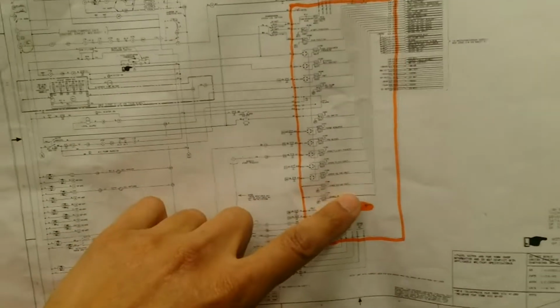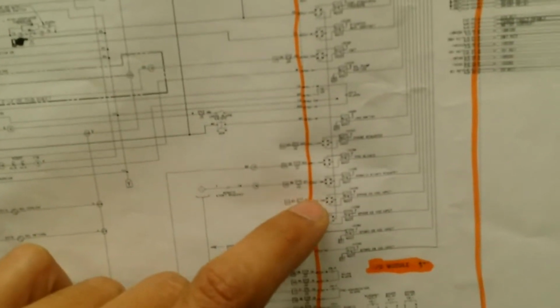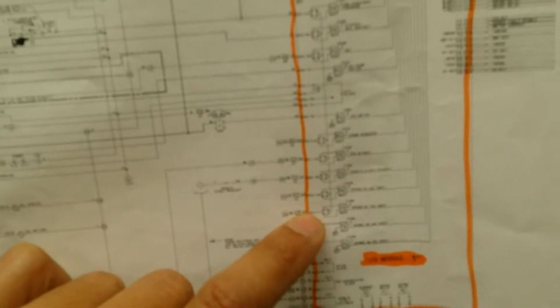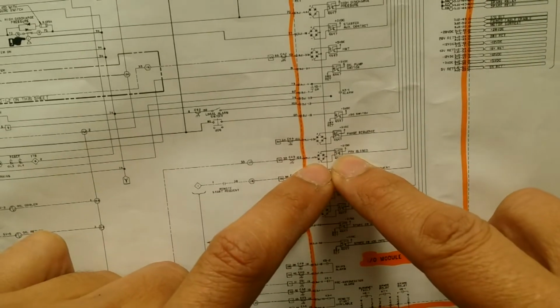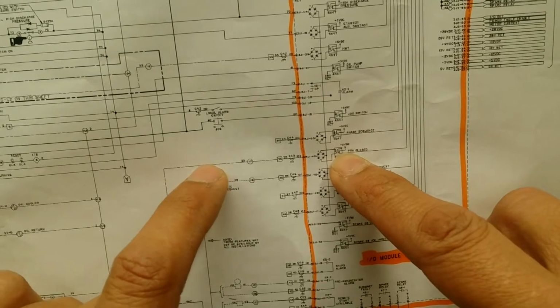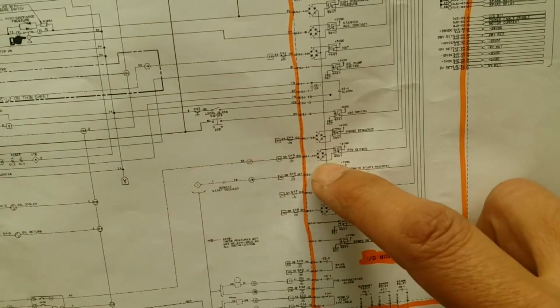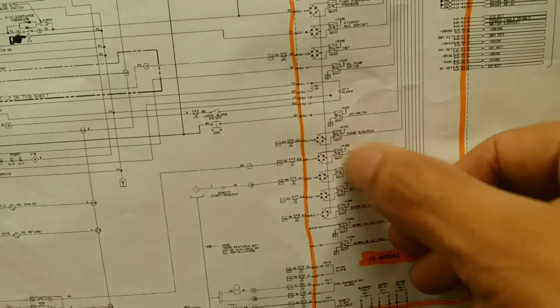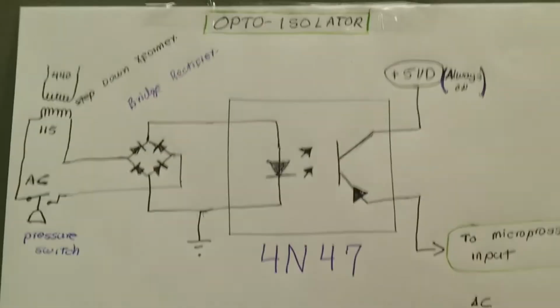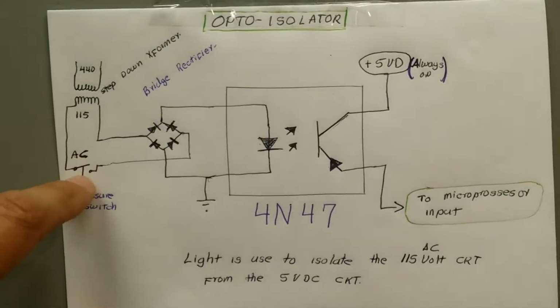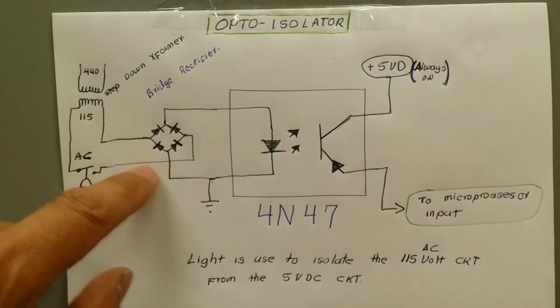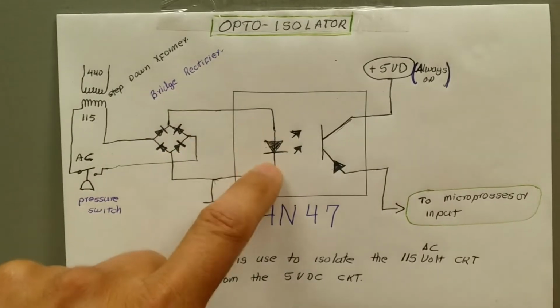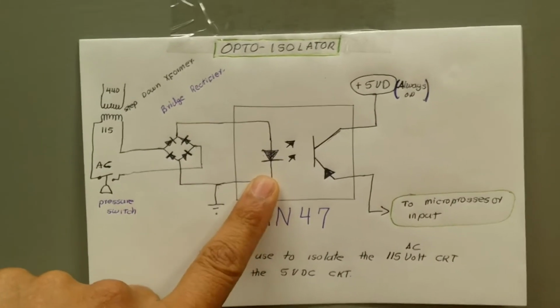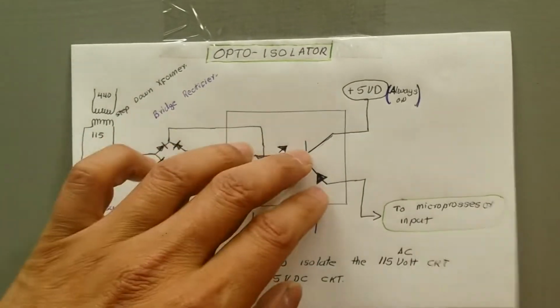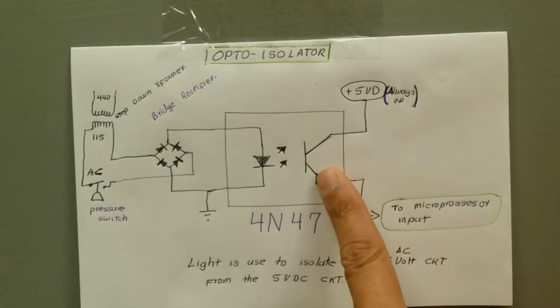Be patient with me, I'm about to start talking about the cards, but before that, one more component. This one is built inside of the circuit card, and it is these opto-isolators. Here we have AC signal coming in, it goes through a full bridge rectifier, and then it gets put into one side over here. I'm going to show you a bigger picture of this. And here it is. For example, this is the pressure switch. When the pressure switch closes, it's putting 115 volts into the bridge rectifier, and really what you're doing is energizing this LED. When the LED turns on, you are optocoupling. That means you're using light to provide an input over here.